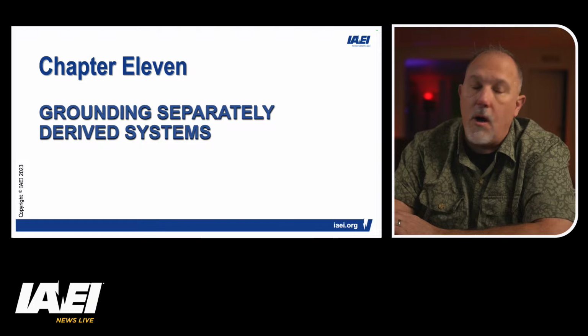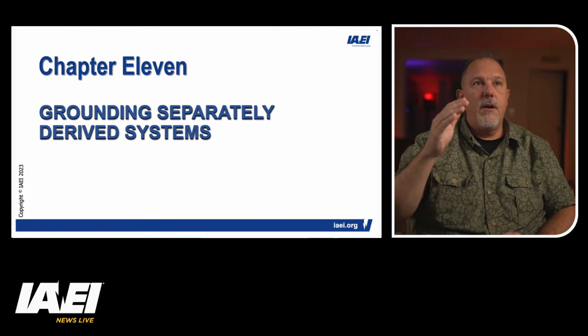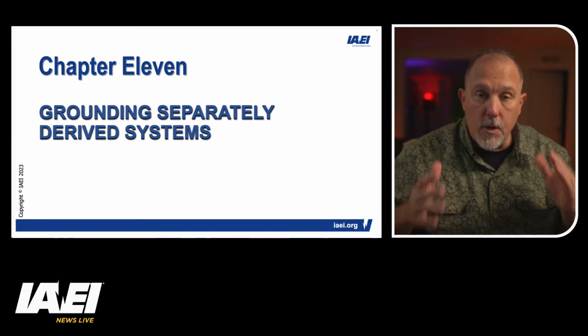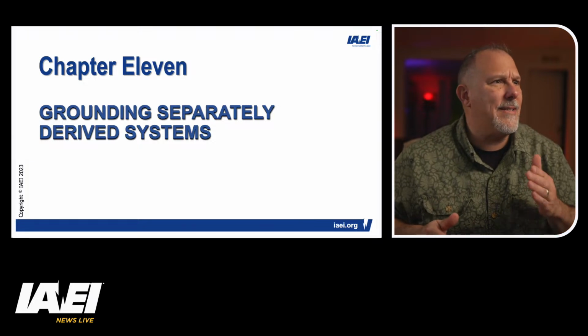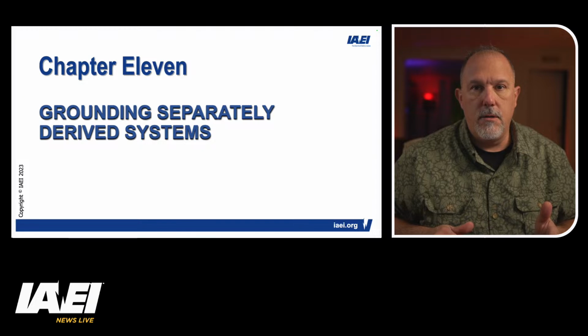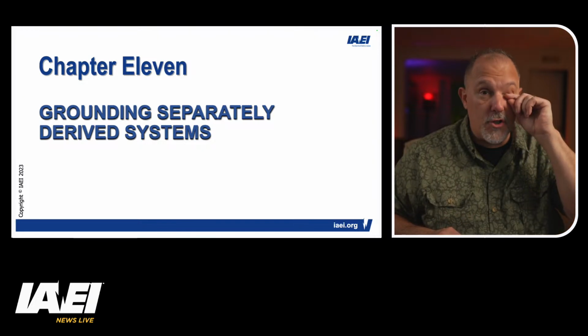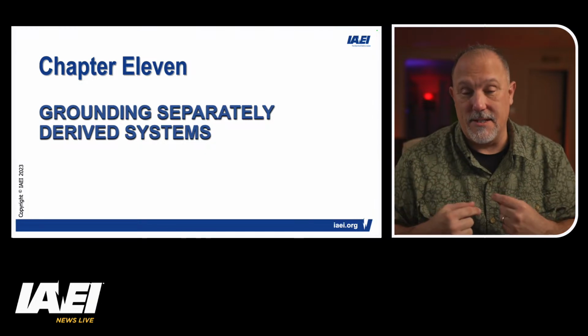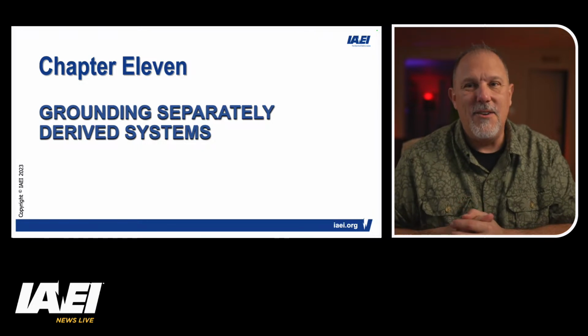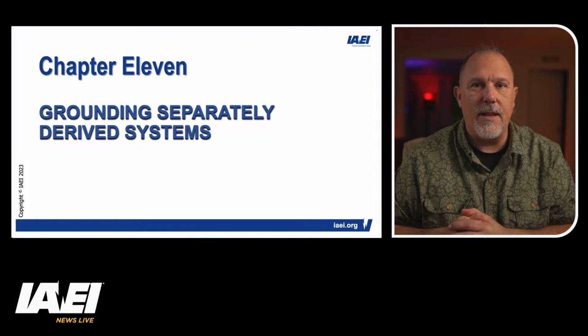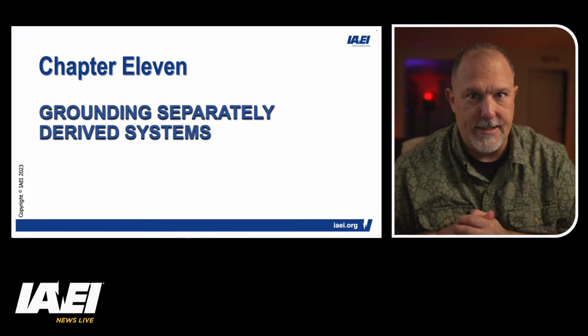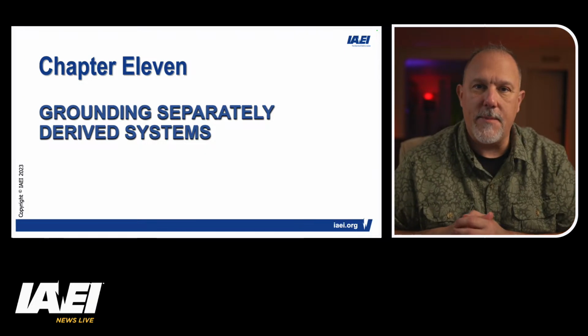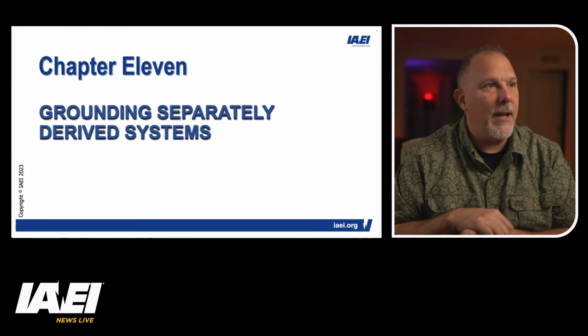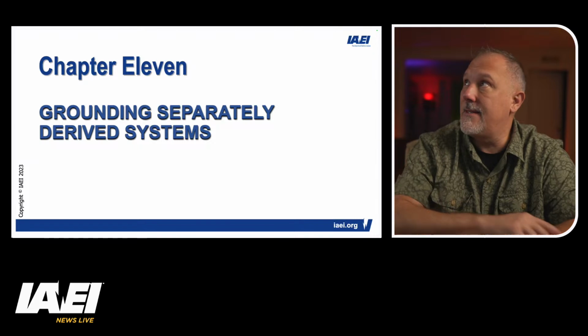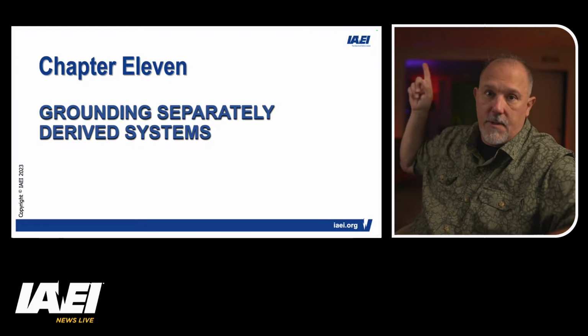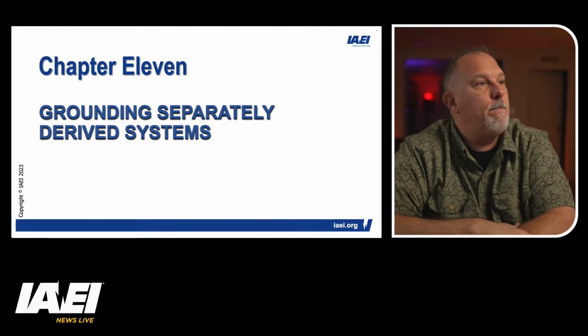Separately derived systems are all around us. I would say pretty much in every power distribution system, we're going to have separately derived systems, all the way down to the doorbell transformer that is probably in most homes. I know we have a doorbell system which is disabled. We disconnected the conductor because when that bell rings, the dogs are a barking. So we don't want that. So you come to my house, you're knocking the old-fashioned way. But we do have a doorbell transformer in the house, y'all, and it's accessible down here in the basement, I believe. It's in the ceiling.